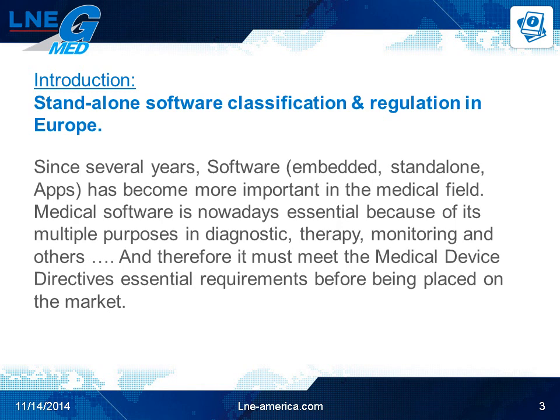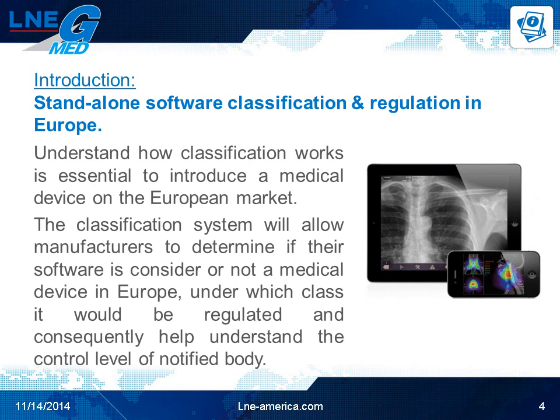For several years, software — be it embedded, standalone, or even apps — has become more important in the medical field. Medical software is essential because of its multiple purposes in diagnostic, therapy, monitoring, and others, and so it must meet the Medical Device Directive's essential requirements before being placed on the market. Like all medical devices, software must be classified to choose the route to demonstrate compliance with the directive. Because software classification rules were designed in the 1990s, they may be difficult to apply to 21st century medical software. For this reason, the European Community published an Interpretive Guidance or MEDDEV for software classification specifically. Understanding how your software is classified is essential for the success of your device in Europe, to ensure the software complies with the directive, and to understand the control level of the notified body.